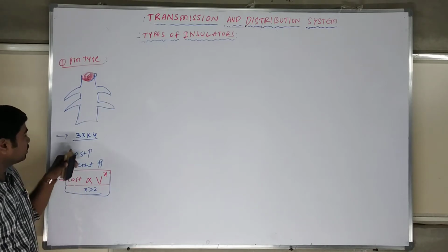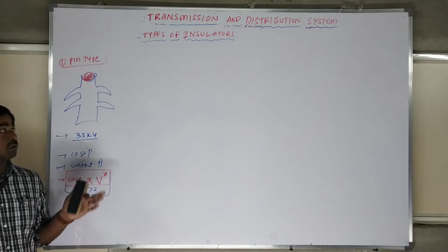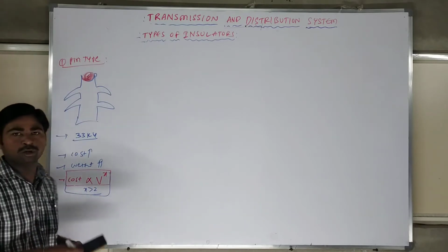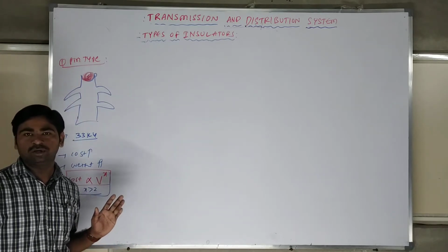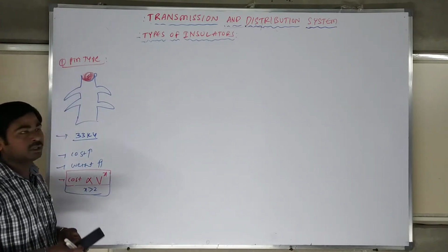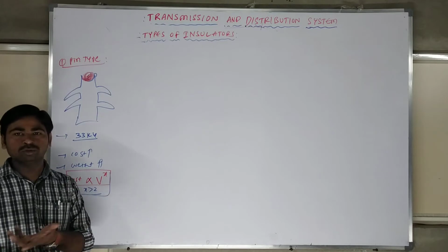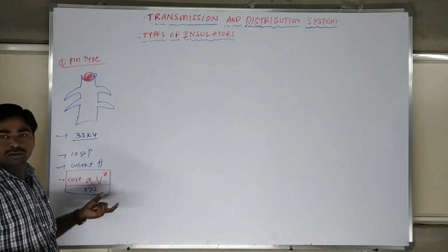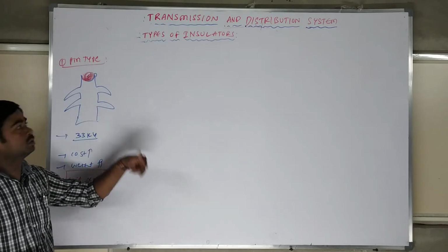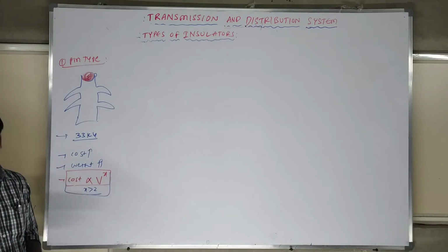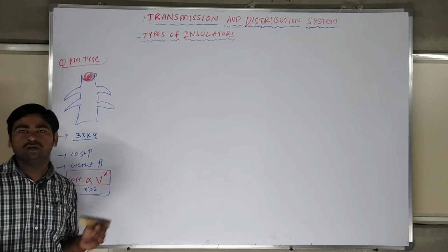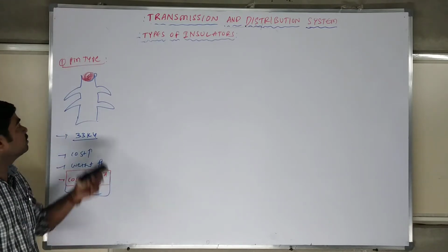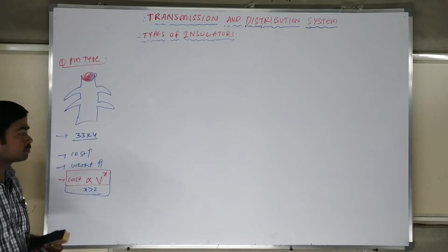So if it is more than 33 kV, there is a problem. Therefore, this insulator is limited to 11 kV in present days, though at most you can use 33 kV. This pin type insulator is very famous in our distribution systems, for home appliances and village backgrounds. We use it on RCC poles for 440 V, 230 V and 11 kV, and also in agriculture fields for farmers.